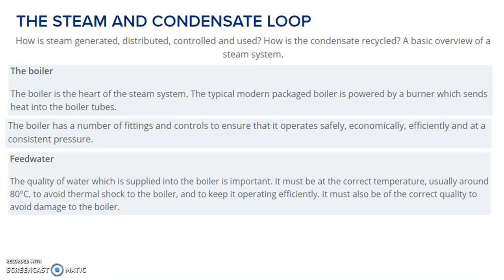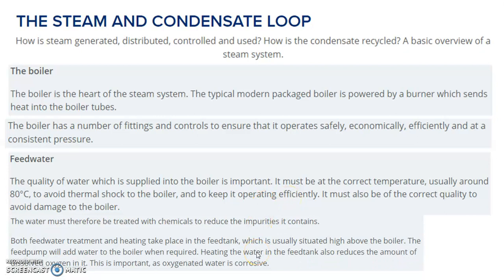Next is feed water. The quality of water supplied into the boiler is important. It must be at the correct temperature, usually around 80 degrees centigrade, to avoid thermal shock to the boiler and to keep it operating efficiently. It must also be the correct quality to avoid damage to the boiler. Feed water must therefore be treated with chemicals to reduce impurities. Both feed water treatment and heating take place in the feed tank, which is usually situated high above the boiler. The feed pump adds water to the boiler when required. Heating water in the feed tank also reduces the amount of dissolved oxygen, which is important as oxygenated water causes corrosion.